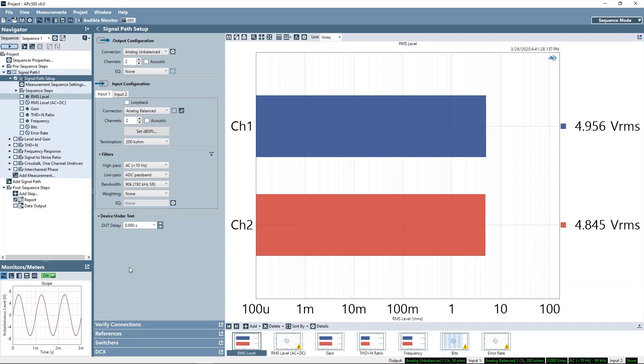The Navigator displays your sequence, which is a list of signal paths, measurements, and results that will be executed from top to bottom when the sequence is run, thus automating the test system. The hierarchy is the APX500 project file: sequences, signal paths, measurements, and results. An APX project may contain multiple sequences, executing multiple signal paths, each with their own settings, measurements, and results.